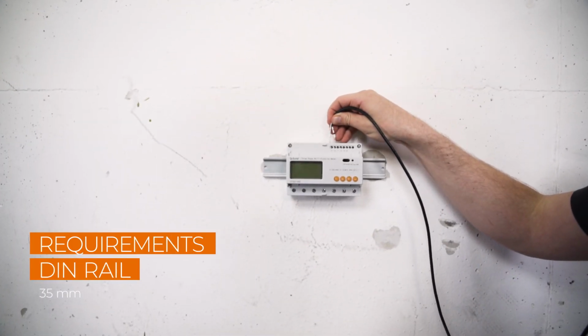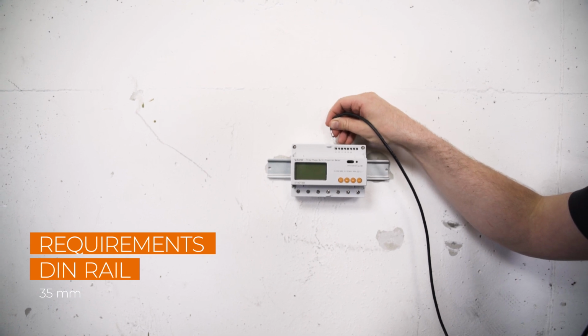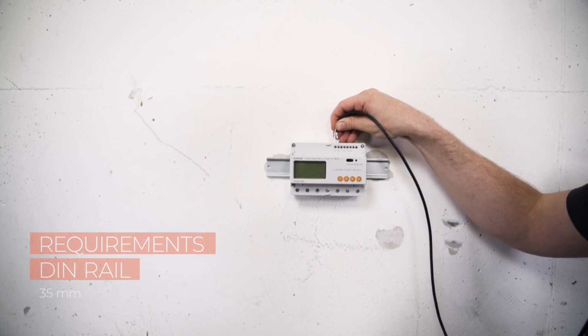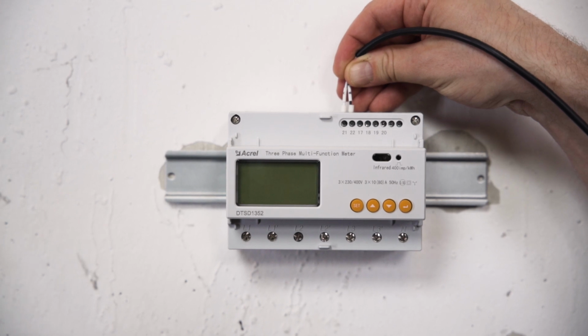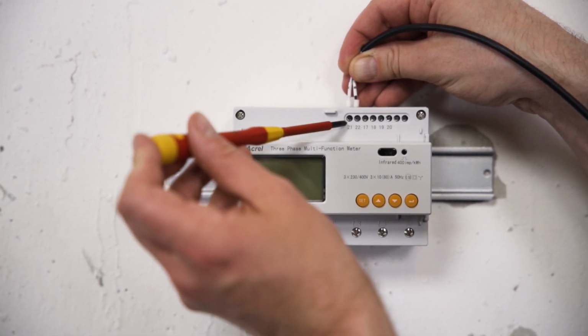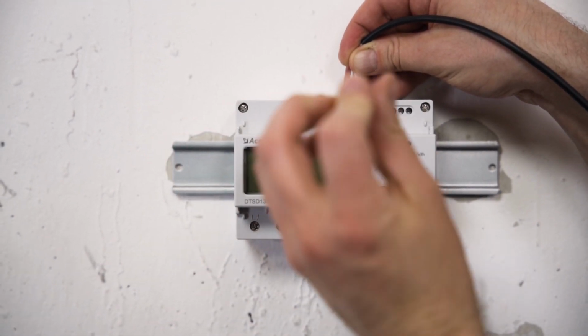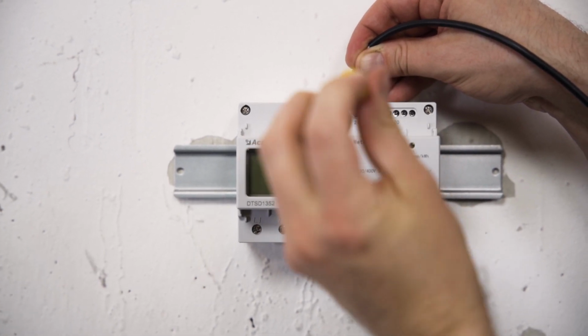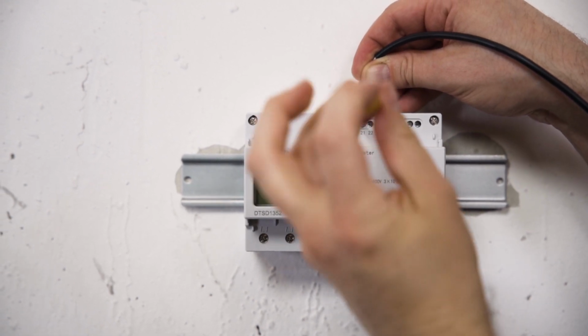The other end of the cable needs to be connected to the smart meter itself. Mount the meter on a DIN rail and connect the communication cable RS485A to pin 21 and RS485B to pin 22. Check the user manual for the connection of the power cables. Now let's jump back to the communication port.